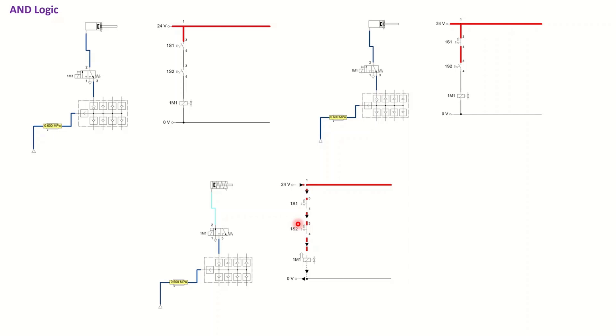If I turn on the first directional control valve manually, the air can pass to the second one, but if the second one is normally closed, we need to push the manual actuator again in order to pass the air to the next step inside the pneumatic system. So here we have the same logic — two switches replacing those directional control valves in series — and we get AND logic. That is how AND logic functions inside electro-pneumatic circuits and how we design AND logic inside electro-pneumatic systems.